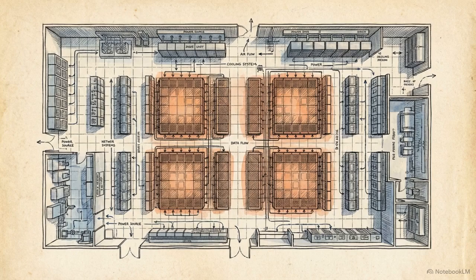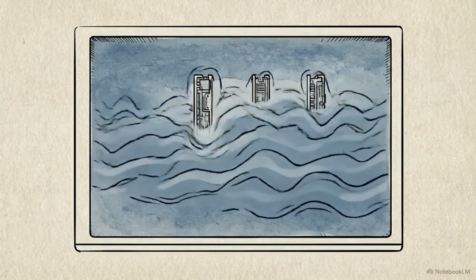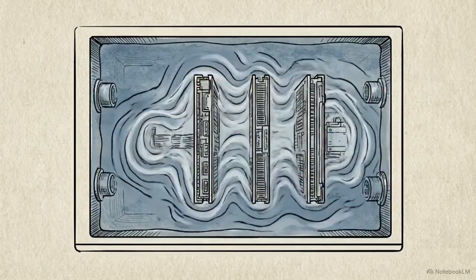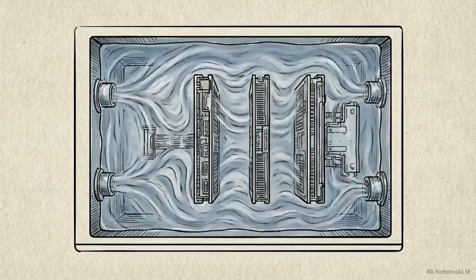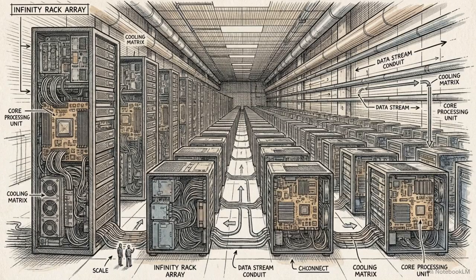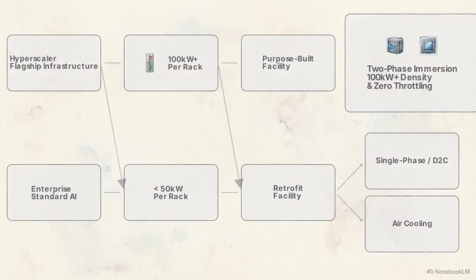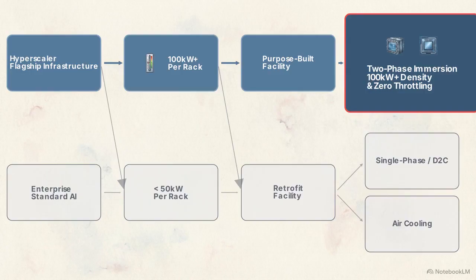Next is the enterprise builder. These organizations are actively commissioning new dedicated zones specifically designed for high-density compute. Single-phase immersion offers the best balance here, trading a manageable operational learning curve for a massive leap to 80 kilowatt density. Finally, there is the hyperscaler. These are the pioneers building flagship AI infrastructure at massive, uncompromising scale. For the hyperscaler, two-phase immersion is required. They have to accept massive upfront costs to guarantee zero thermal throttling while pushing 100+ kilowatts of power continuously.